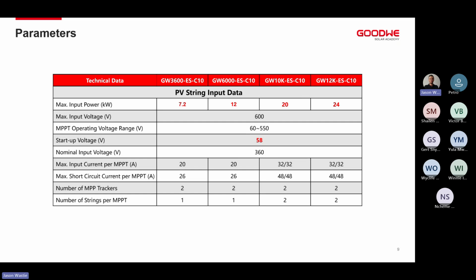Where this can become very beneficial is if we look at it from a sales aspect. The inverter starts operating at a much earlier time in the day because the voltage range starts at a lot lower. So there are 2 things we can look at. 1, if they are price conscious and not too worried about the amount of load that they've got during the day, and they don't need a massive PV array, we can add fewer panels. As long as we get as close to the nominal input voltage of 360 volts, we can put in fewer panels and use that to charge our batteries up.